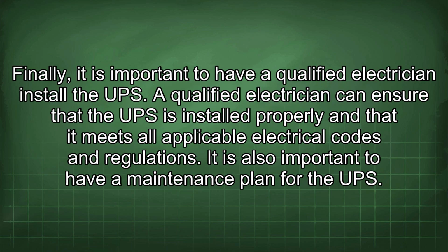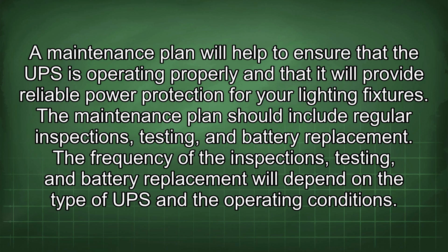Finally, it is important to have a qualified electrician install the UPS. A qualified electrician can ensure that the UPS is installed properly and that it meets all applicable electrical codes and regulations. It is also important to have a maintenance plan for the UPS. A maintenance plan will help to ensure that the UPS is operating properly and that it will provide reliable power protection for your lighting fixtures. The maintenance plan should include regular inspections, testing, and battery replacement. The frequency of the inspections, testing, and battery replacement will depend on the type of UPS and the operating conditions.